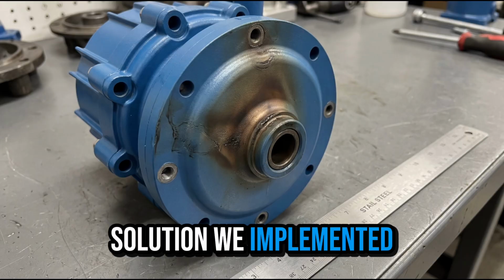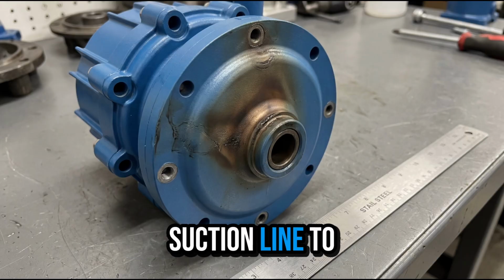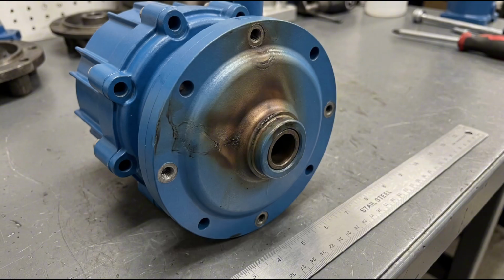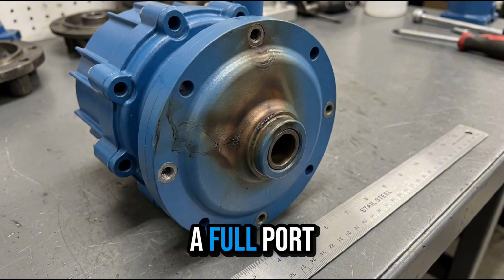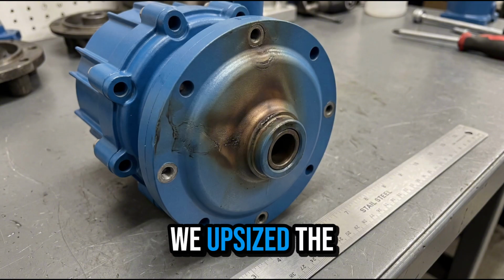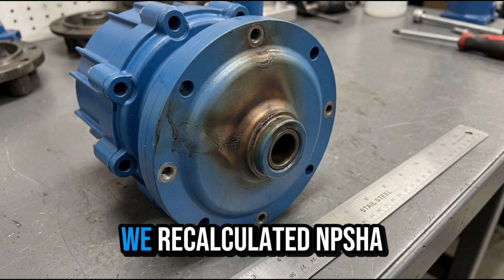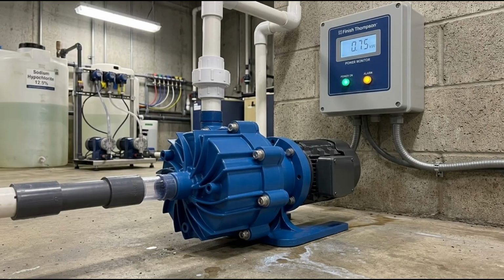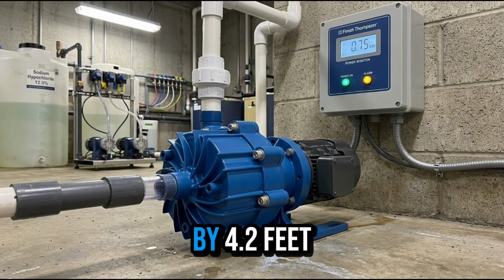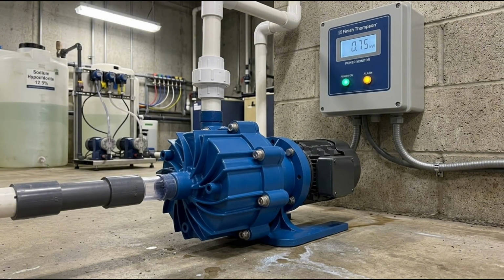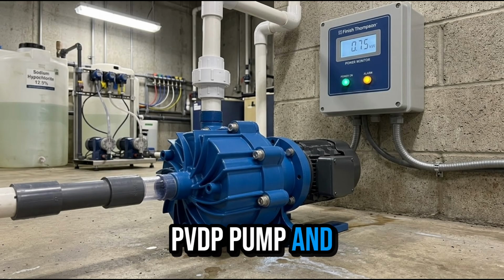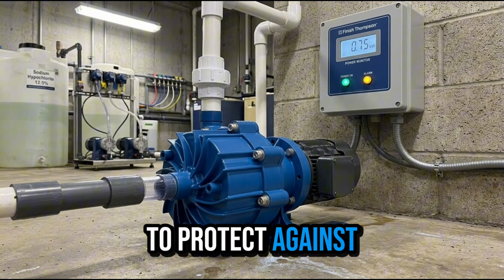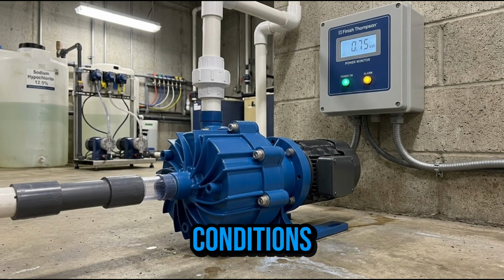Here is the solution we implemented. We rerouted the suction line to eliminate the low point. We replaced the gate valve with a full port ball valve. We upsized the suction piping. We recalculated NPSHa at worst case conditions. It exceeded NPSHr by 4.2 feet. We specified a PVDF pump and added a power monitor to protect against dry run and abnormal conditions.